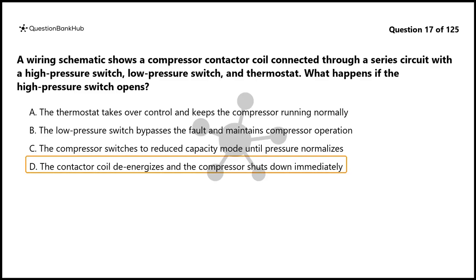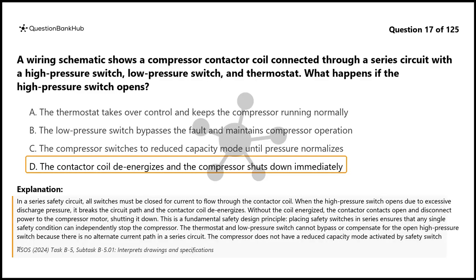The correct answer is D. In a series safety circuit, all switches must be closed for current to flow through the contactor coil. When the high-pressure switch opens due to excessive discharge pressure, it breaks the circuit path and the contactor coil de-energizes. Without the coil energized, the contactor contacts open and disconnect power to the compressor motor, shutting it down.